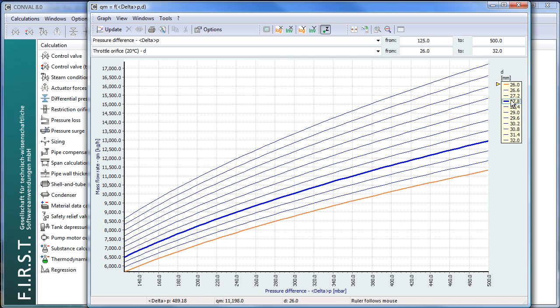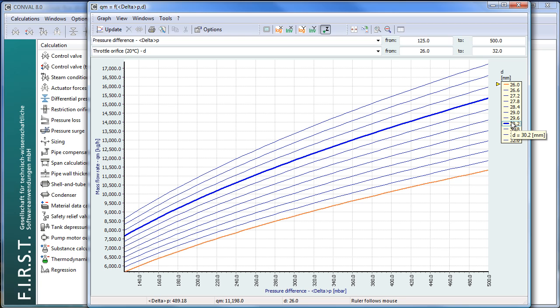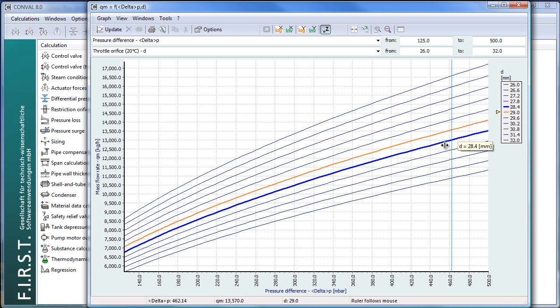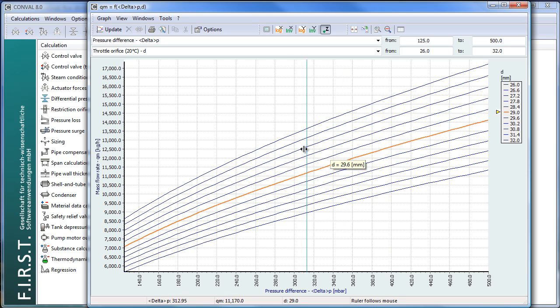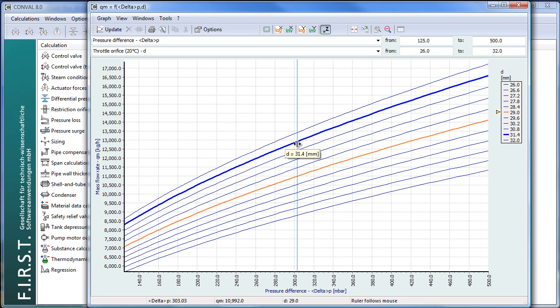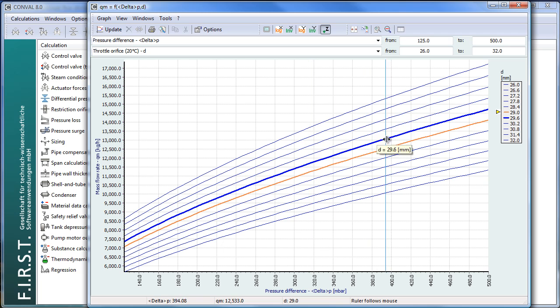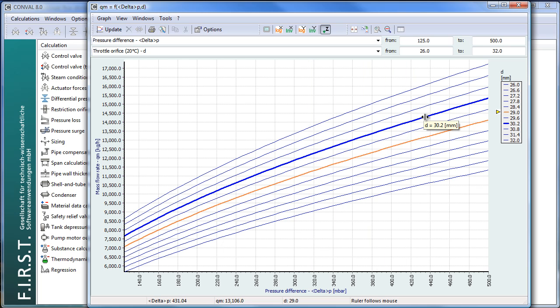It yields a family of curves. In the legend, of course you can reverse, you can change the scale, log, whatever. But in this example, let's assume 29, which is about the orifice plate that we have, and so again you see the effects of the orifice diameter as well as the delta P on the mass flow.